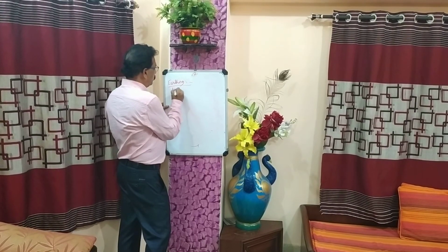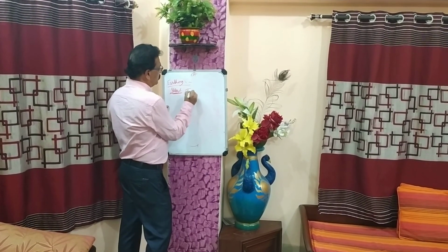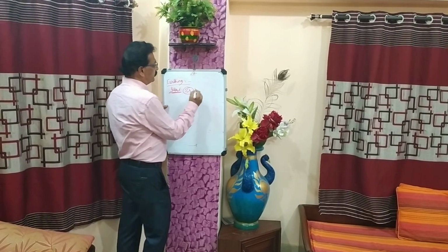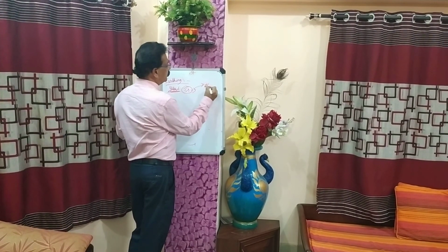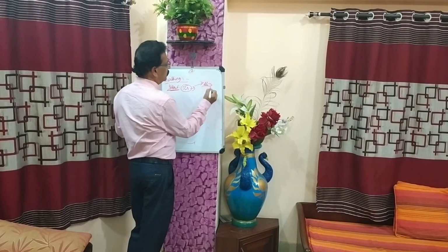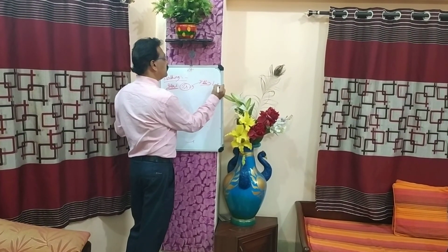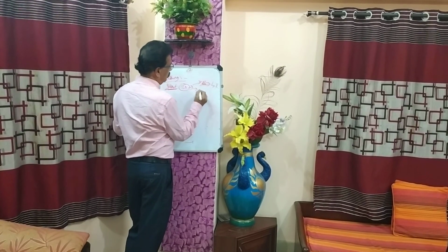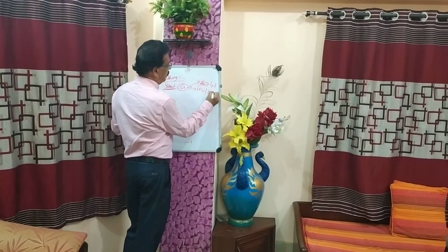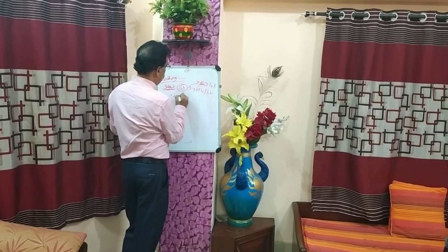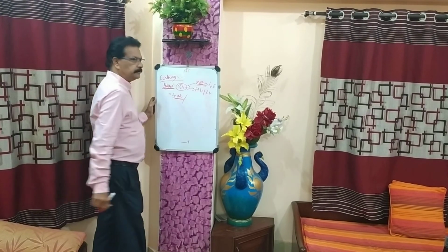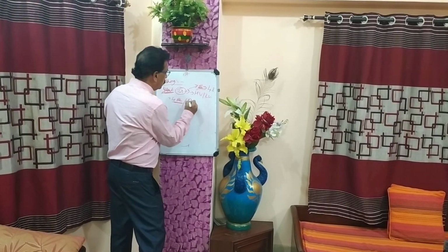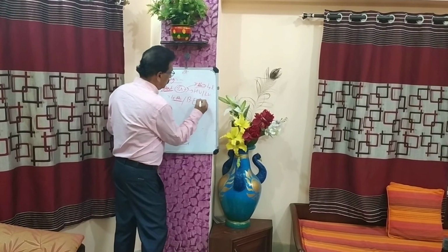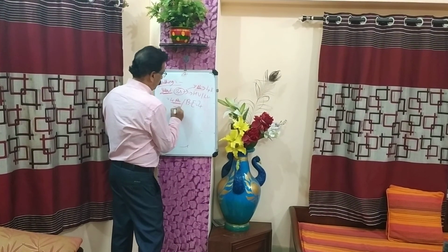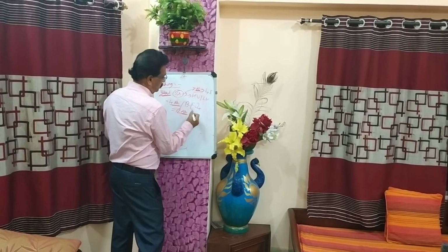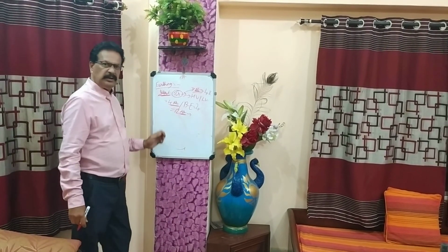In the yard, first thing I'll tell you - where the transformer is there, for this transformer, for your neutral things, you should have 4 earthings. Here on HV side and LV side, you require 4 number earth. Body earth you require 4 number. Total 12 numbers are compulsory for the transformer.